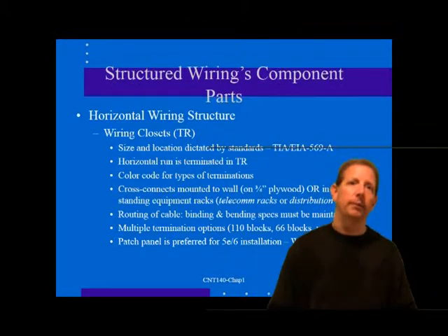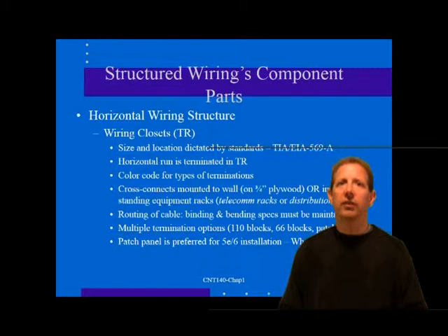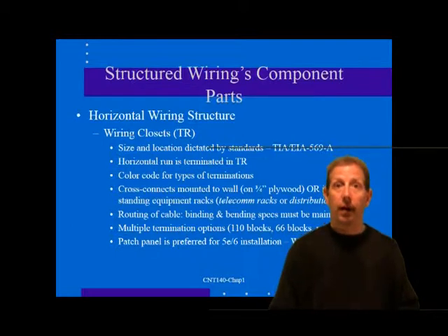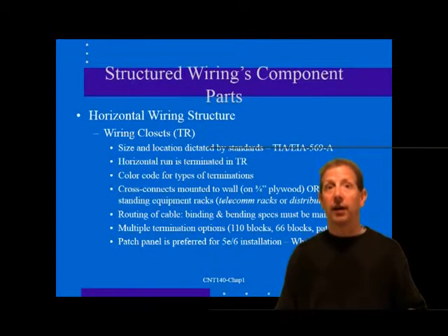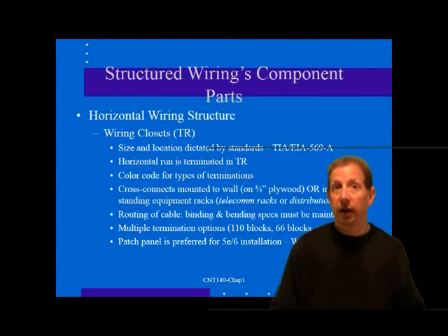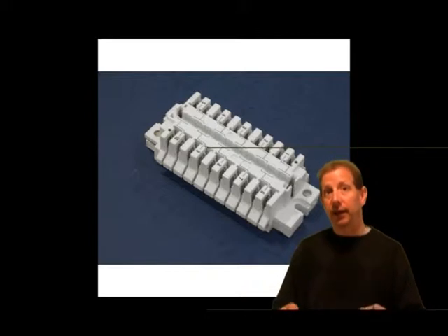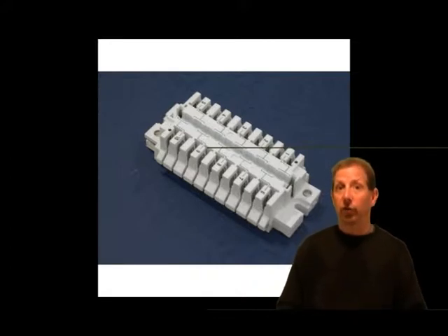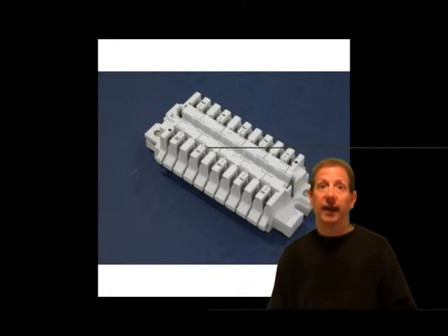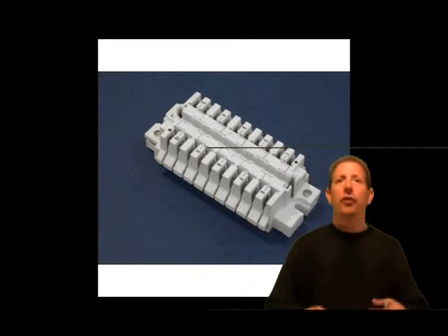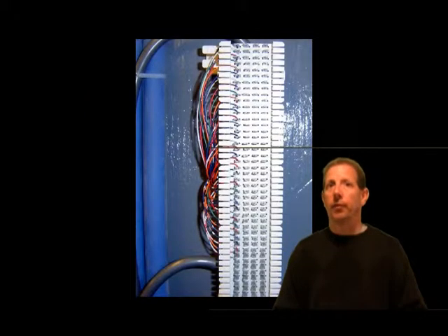Cat 5e is now the minimum specification. Insulation displacement terminations (IDC) use a split metal contact upon which the insulated wire is forced, cutting through the insulation and making metal-to-metal contact with the copper wire. Several types of insulation displacement connectors exist, including modular snap-together IDC jacks, modular 110-type IDC jacks, and older 66-type IDC jack plates. Except for the 66-type, jacks are commonly available in models certified to Cat 5e performance standards.